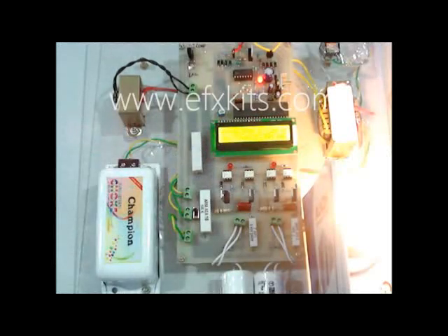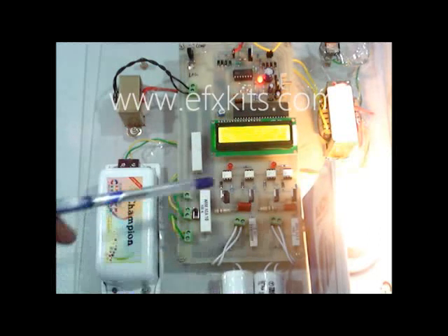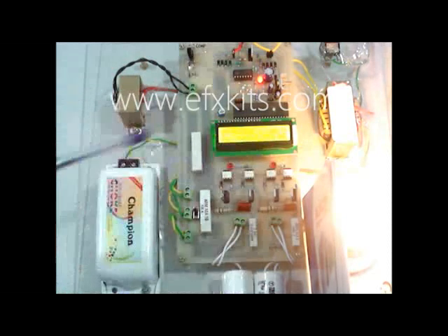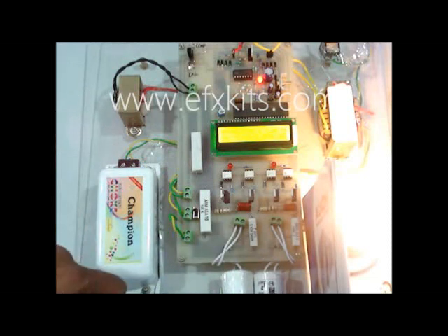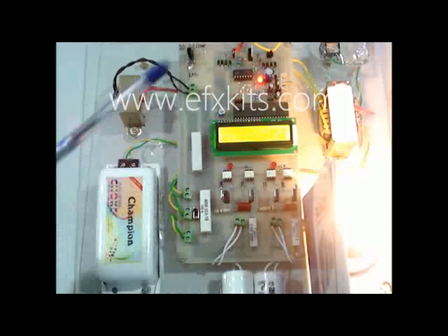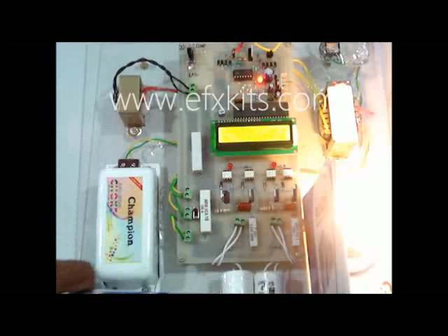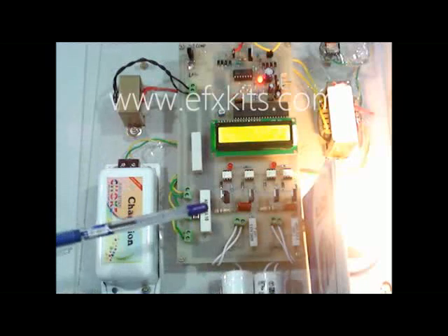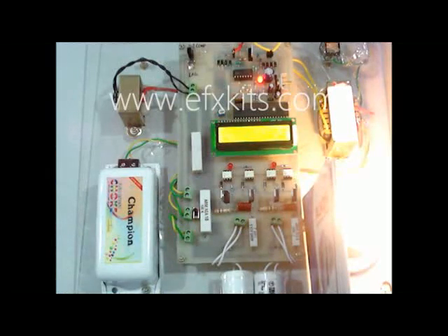Based on this, the power factor has been calculated, and we will notice that since the power factor is of this nature, the capacitors will automatically get switched on, which we can see from this LED glowing. And if one LED glows, we will come to know that one of the capacitors is switched on, and if the second LED glows also, then we will know that both the capacitors are switched on. Now at this juncture, we will find that only one capacitor will be switched on depending on the power factor, which we find here.